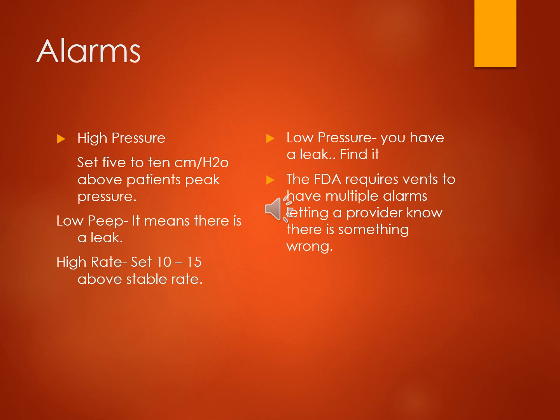Alarms are high pressure alarms. That's going to keep us from overpressurizing the lungs, so it pops off, say, if the patient's coughing really hard, and we don't want those peak pressures to be super high. If the patient's compliance is decreasing or their resistance is increasing, it's going to let us know: hey genius, pay attention to your numbers on your vent and make sure it's set correctly. So we're going to set 5 to 10 centimeters of water pressure above the patient's peak airway pressure right now. That will hopefully give us an idea that things are changing.